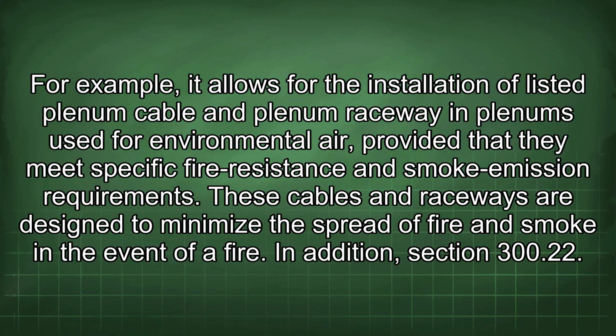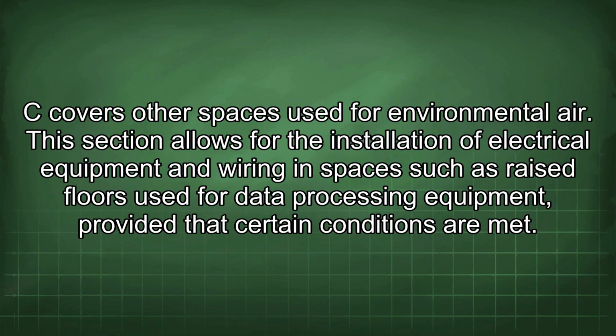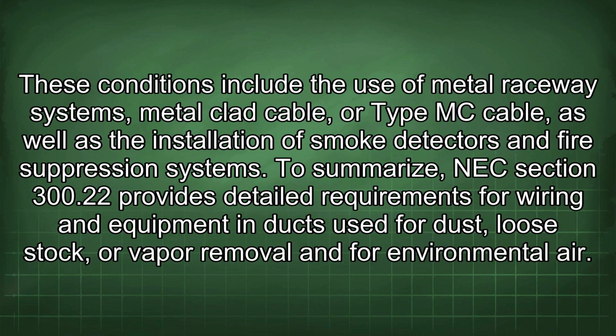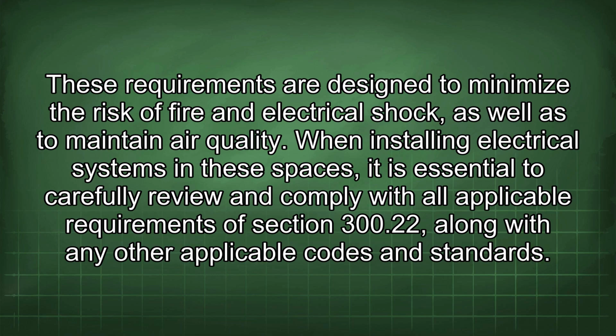In addition, Section 300.22(C) covers other spaces used for environmental air. This section allows for the installation of electrical equipment and wiring in spaces such as raised floors used for data processing equipment, provided that certain conditions are met. These conditions include the use of metal raceway systems, metal-clad cable, or Type MC cable, as well as the installation of smoke detectors and fire suppression systems. To summarize, NEC Section 300.22 provides detailed requirements for wiring and equipment in ducts used for dust, loose stock, or vapor removal and for environmental air. These requirements are designed to minimize the risk of fire and electrical shock, as well as to maintain air quality.